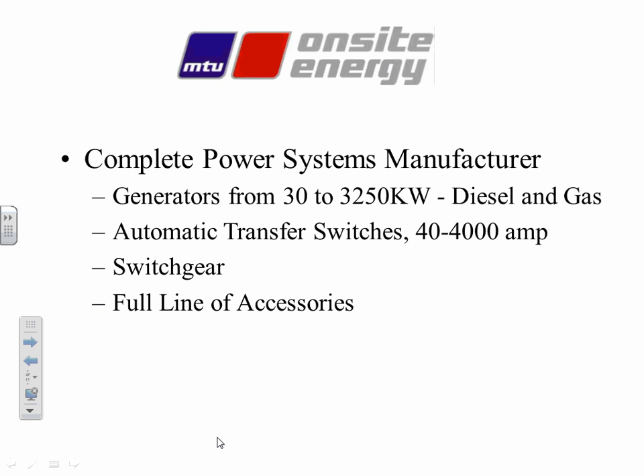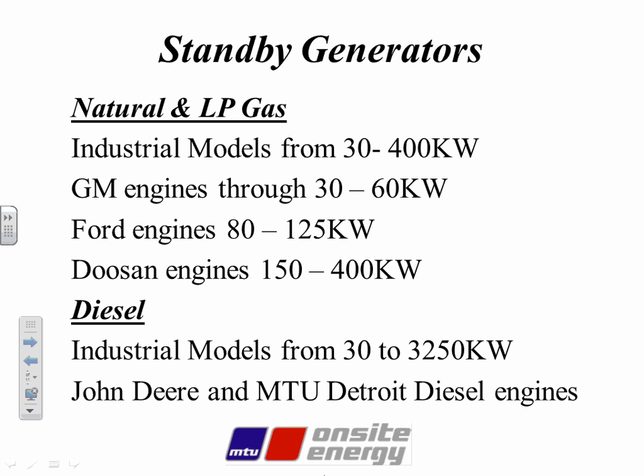We are a complete power systems manufacturer. Again, what that means is we sell the generator sets, gas and diesel, in a range from 30 kilowatts up to 3,250 right now. Automatic transfer switches from 40 amps up to 4,000 amps, including service entrance rated stuff. Switch gear, paralleling switch gear and distribution if we need it. And a full line of accessories. Those might be remote radiators, and now oxidation catalysts and all kinds of things like that. Battery chargers, vibration equipment, vibration isolators.